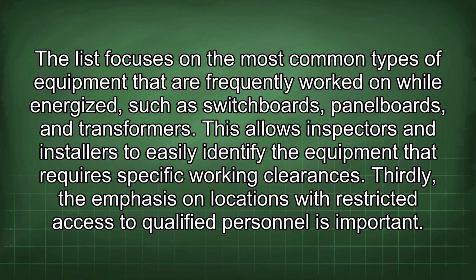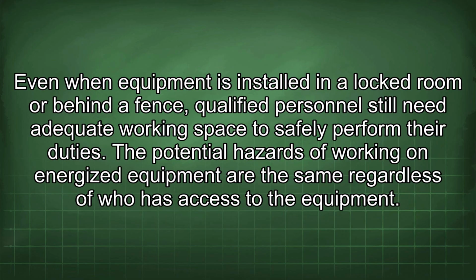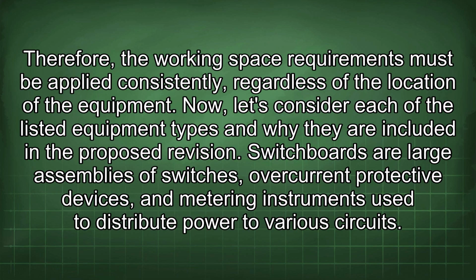Thirdly, the emphasis on locations with restricted access to qualified personnel is important. Even when equipment is installed in a locked room or behind a fence, qualified personnel still need adequate working space to safely perform their duties. The potential hazards of working on energized equipment are the same regardless of who has access to the equipment. Therefore, the working space requirements must be applied consistently, regardless of the location of the equipment.